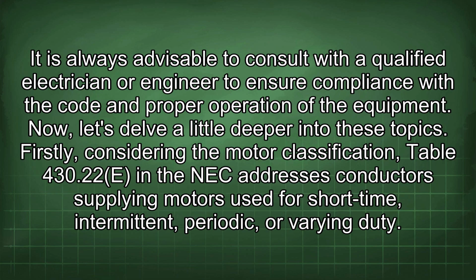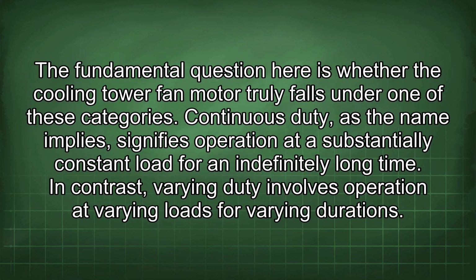Firstly, considering the motor classification, Table 430.22e in the NEC addresses conductors supplying motors used for short time, intermittent, periodic, or varying duty. The fundamental question here is whether the cooling tower fan motor truly falls under one of these categories. Continuous duty, as the name implies, signifies operation at a substantially constant load for an indefinitely long time. In contrast, varying duty involves operation at varying loads for varying durations.